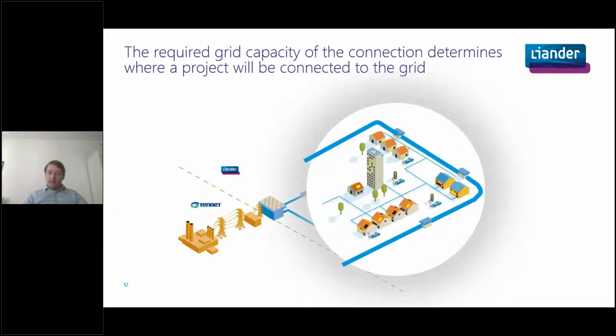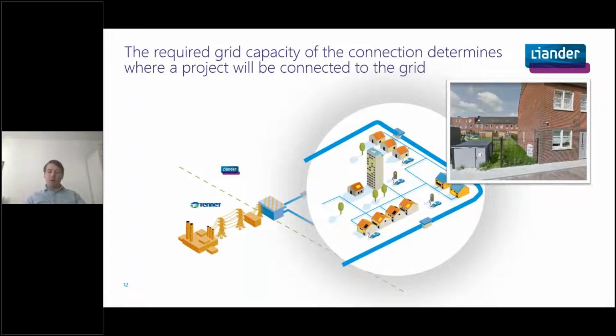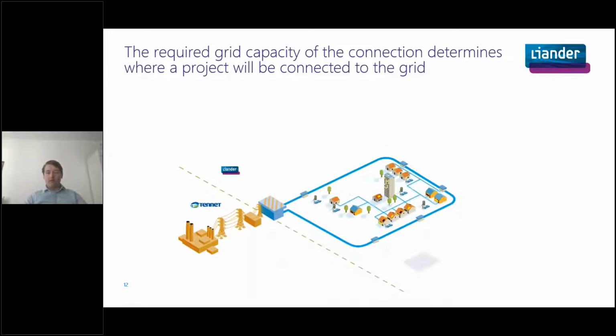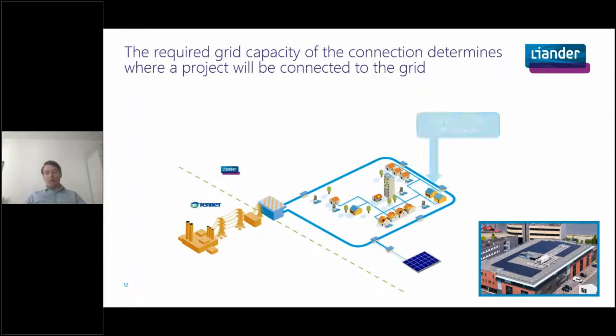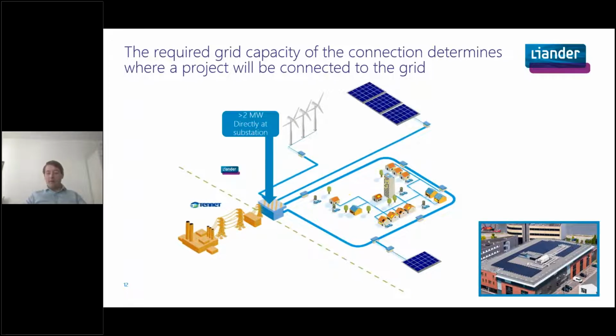So where are most clients connected to the grid? Well, it depends—the grid capacity of the connection determines where a project will be connected. If you zoom into neighborhoods, you find mainly smaller connections: from 0 kilowatts up to 55 kilowatts, all connected to the low voltage network. Somewhat larger projects, like smaller solar farms or rooftop solar, are connected to the medium voltage network, between 160 kilowatts and 2 megawatts. Everything above 2 megawatts is connected directly to a high voltage/medium voltage transformer substation—think larger wind farms and solar farms with their own electricity connection to that grid.